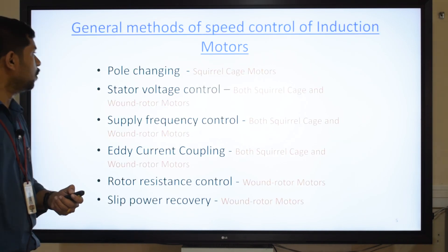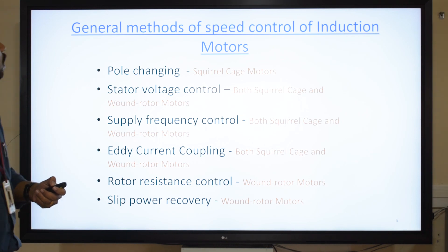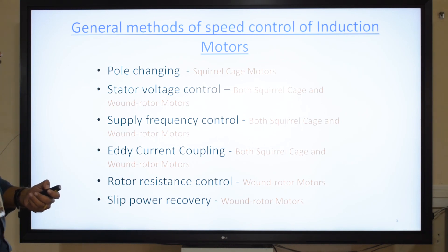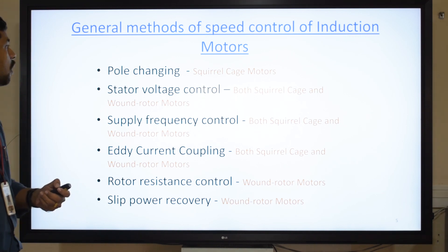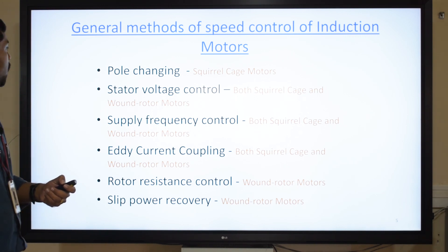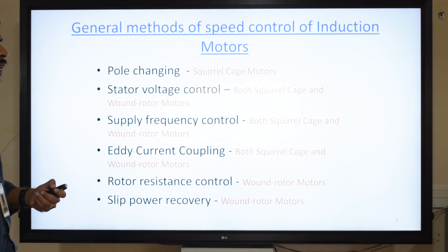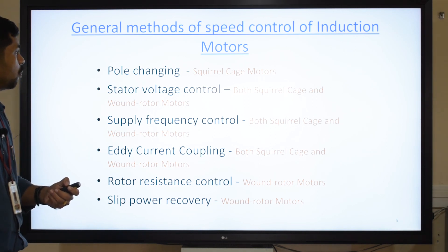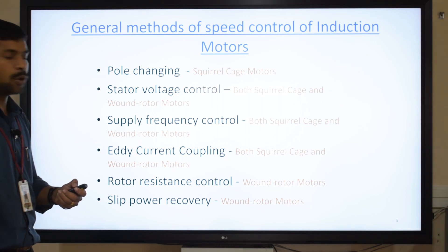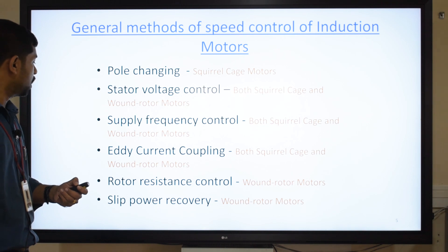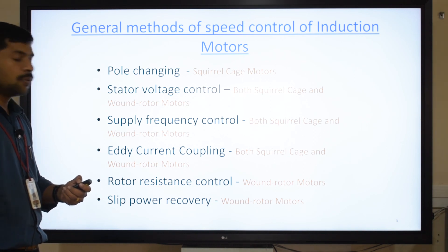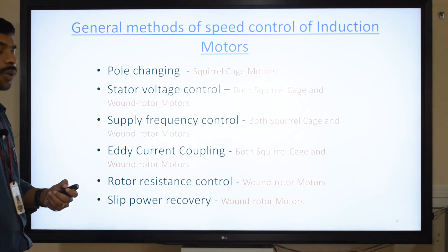There are a few methods for control of induction motor. The first one is the pole changing method, which can be used only for squirrel cage type motors. Then we have stator voltage control, supply frequency control, and eddy current coupling, which can be used for both squirrel cage and wound type motors. And we have rotor resistance control and slip power recovery schemes, which can be used only for wound rotor type motors.